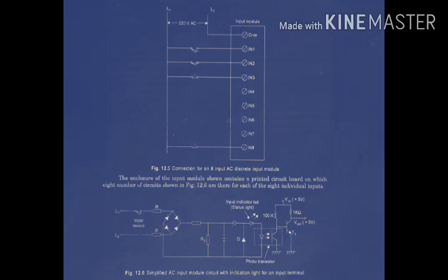Here is 220V AC. For 24V DC, positive and negative are used. For example, in our case we are using push button, limit switch, proximity switch — all at 220V AC. This is the connection diagram. Now what is this circuit diagram? This is figure 12.6: simplified AC input module circuit with indication light for one input terminal. L1 and L2 are the supply lines. The working is the same for DC, only the supply changes.